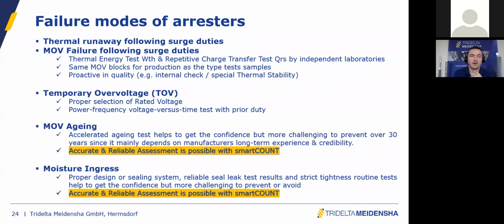So I would say that typical failures that have been experienced on site are moisture ingress, which is much more common on the distribution class than on the high voltage. I know the reason, but this is not the place for this topic. And actually, the failure rate in general for high voltage surge arresters, if they come from responsible manufacturers, is quite low. This is actually a general consensus.